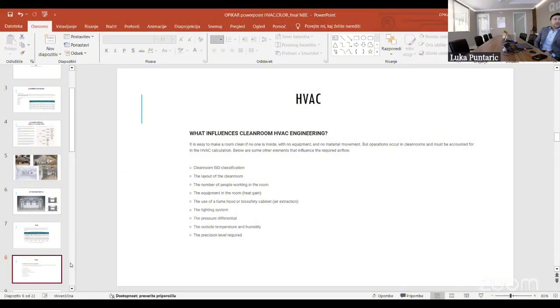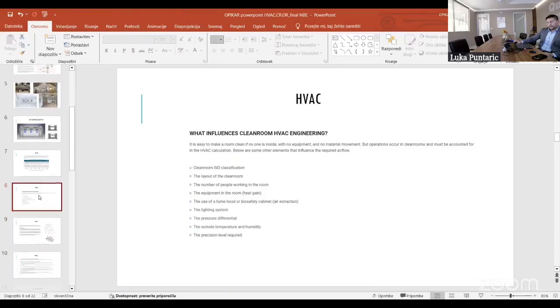HVAC. What influences clean room HVAC engineering? We have different things we need to take care of. First of all, we need to define the clean room ISO classification. We always try, in collaboration with the client, to prepare a user requirement specification and room data sheets, where the most important things are shown, like the clean room ISO classification, the layout of the clean room, and the number of people working in the room, which also matters. The equipment in the room also matters, because all the equipment and the lighting gain heat that we need to cool down and get rid of with our HVAC systems. So pressure differential, temperature and humidity: those are the things that we need to take care of.